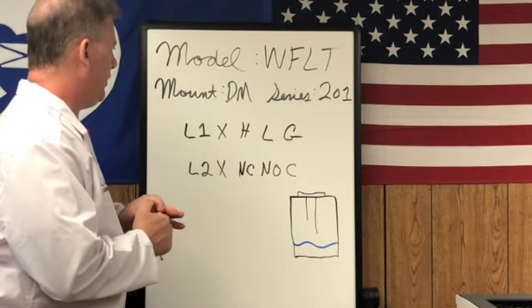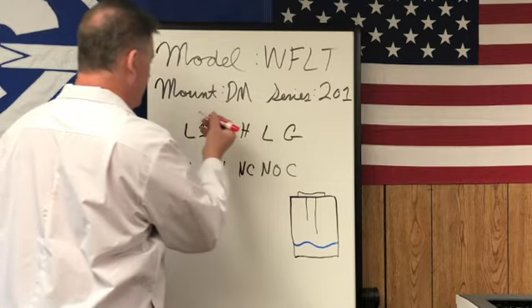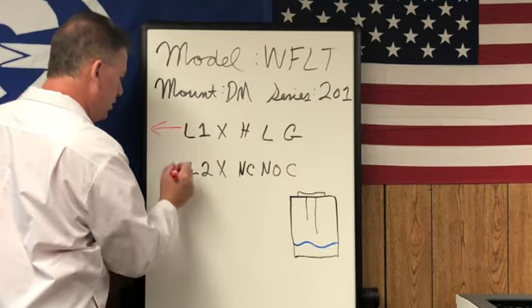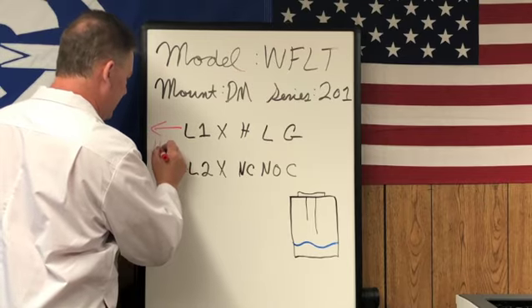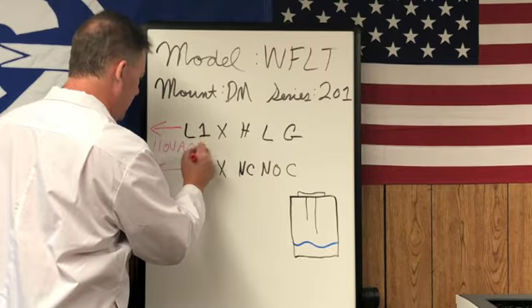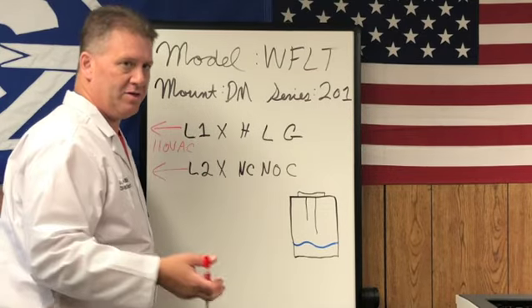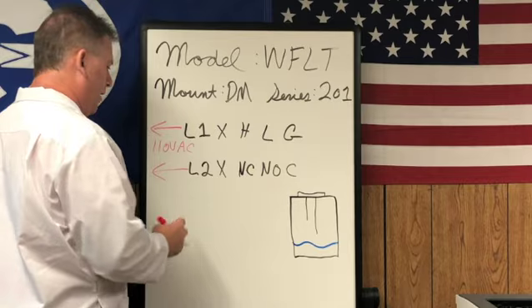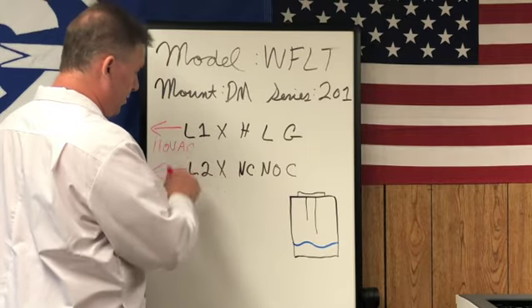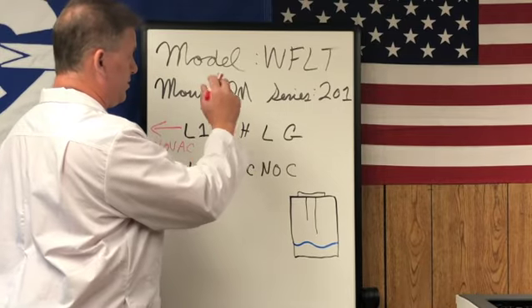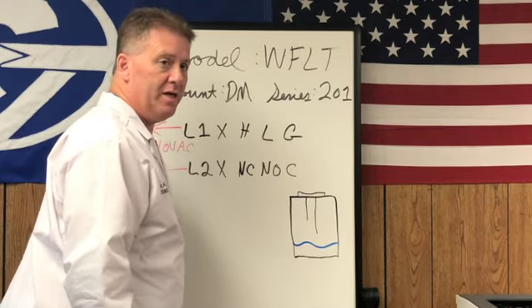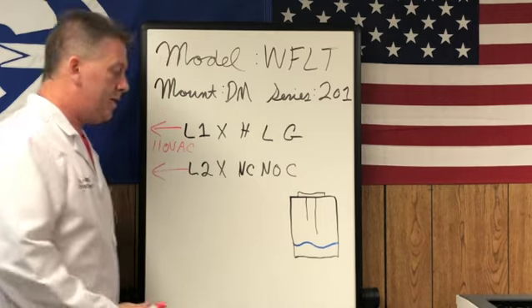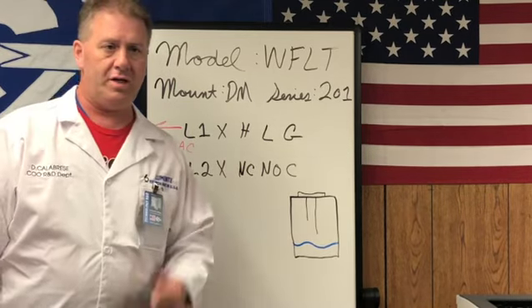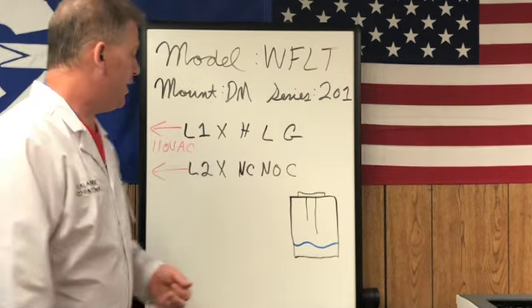The way it's laid out, you have two blank spaces here. On the left-hand side is your line voltage, so we're going to take L1 and L2 to 110 VAC. I picked 110 volts because that's also the most popular one. Just to say something about the line voltage, we offer the standard WFLT level controls in 24 volts AC, 110, and 240.